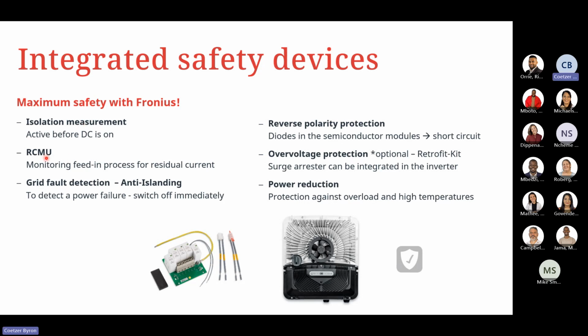Your RCMU, so monitoring of the feeding process for any residual currents that are present, as well as grid fault detection, so your anti-islanding detection to detect a power failure and then switch off the inverter immediately.